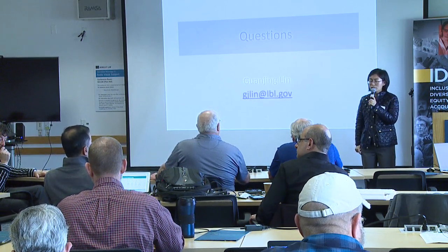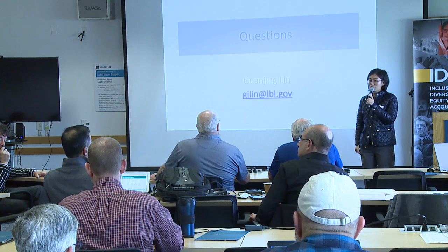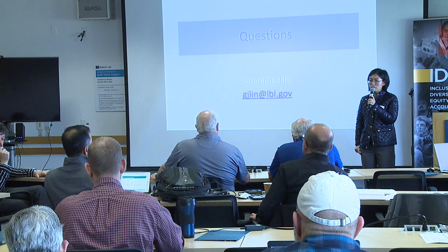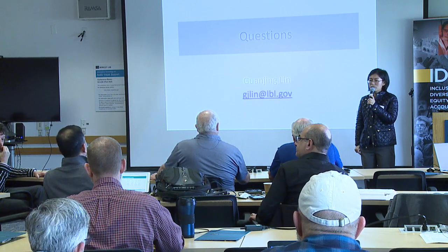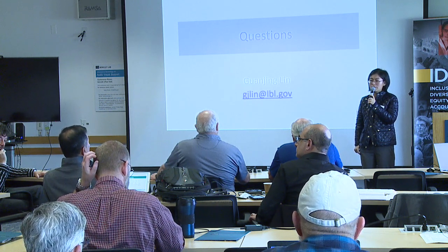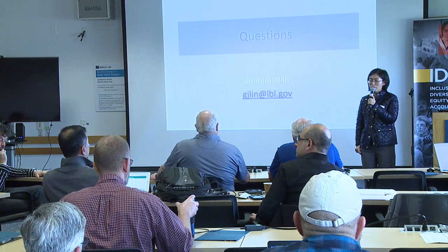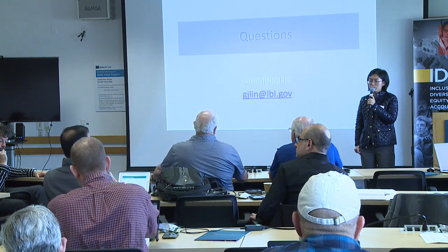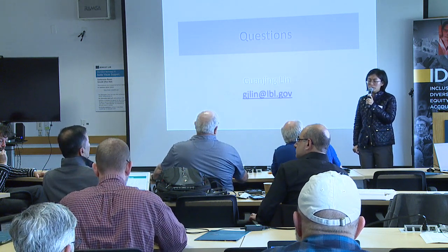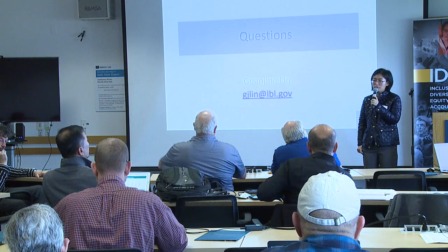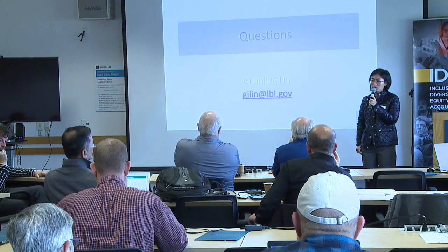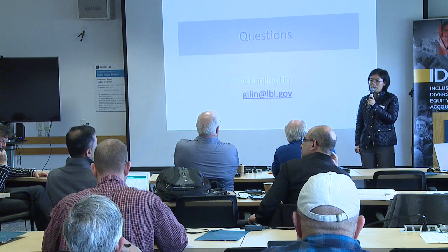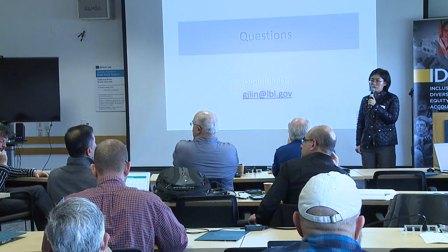And a lot of times we know they only need a fraction of that data. And so what happened, it clogs our network. We found out when we trend points, we were having a hard time grabbing that data on our end because the network traffic was so congested.